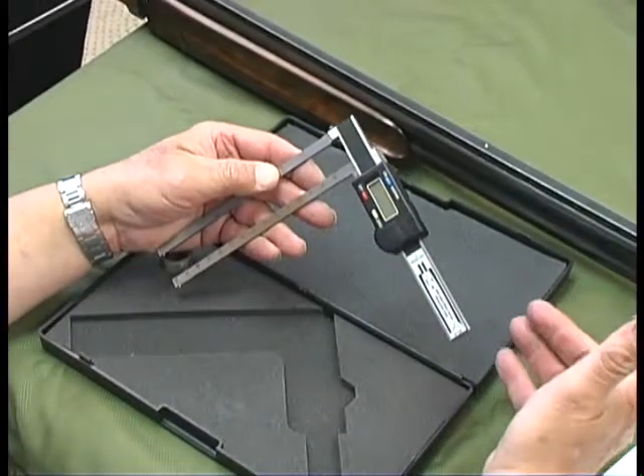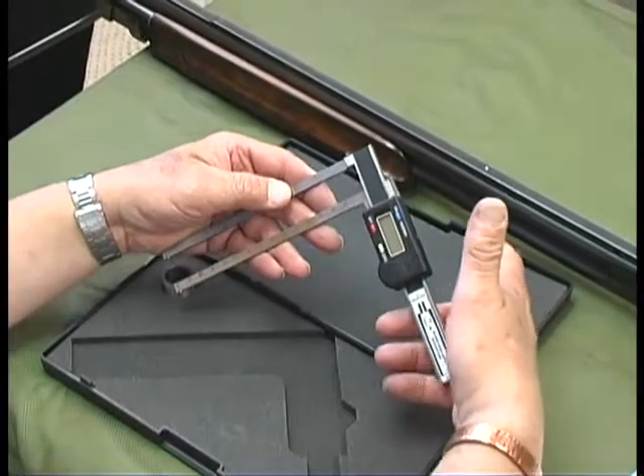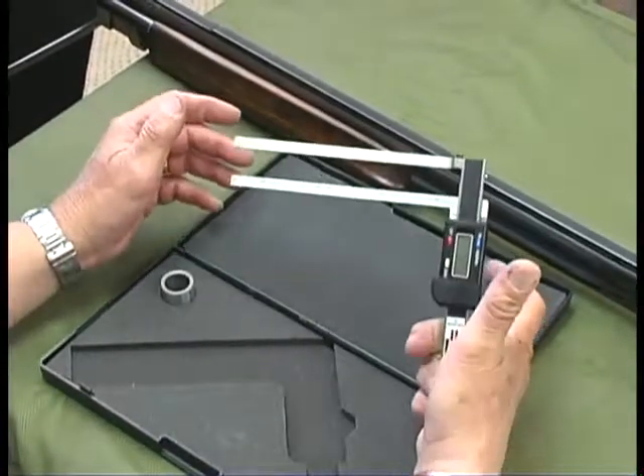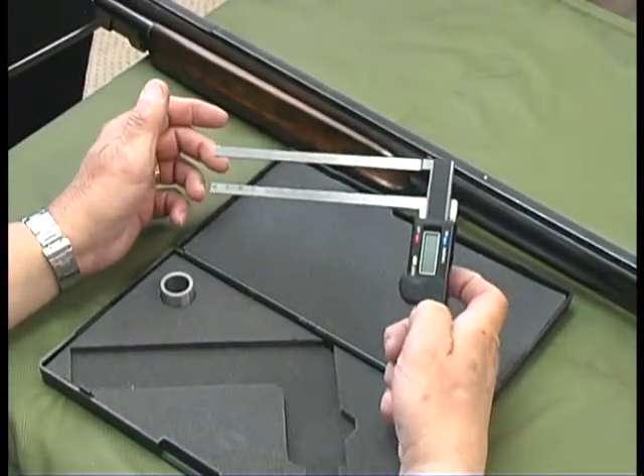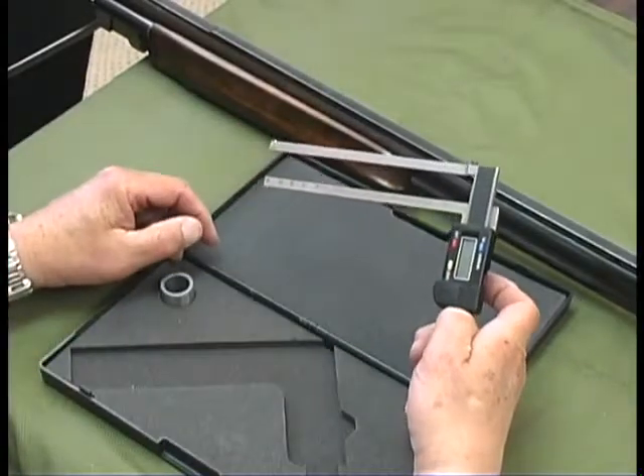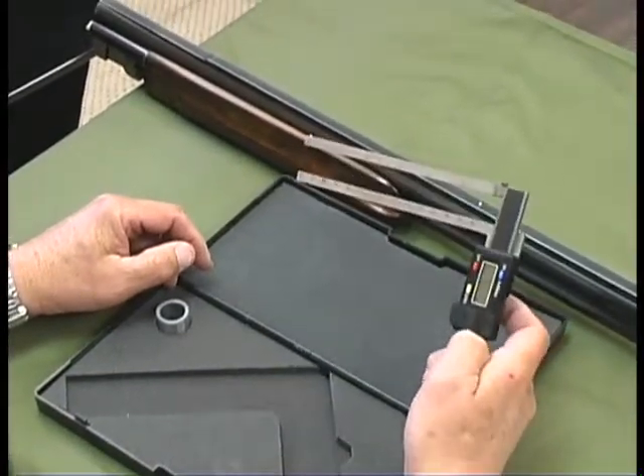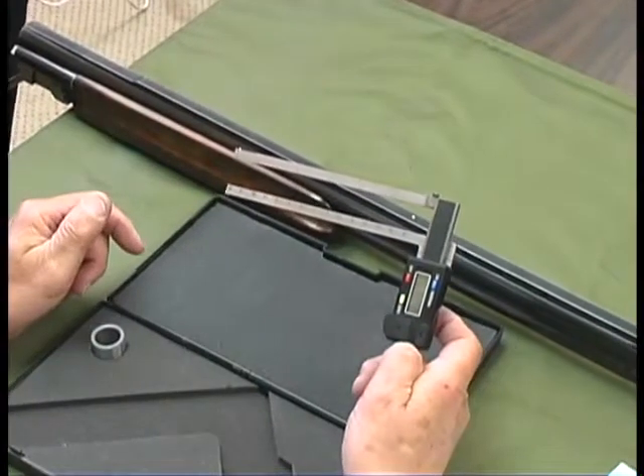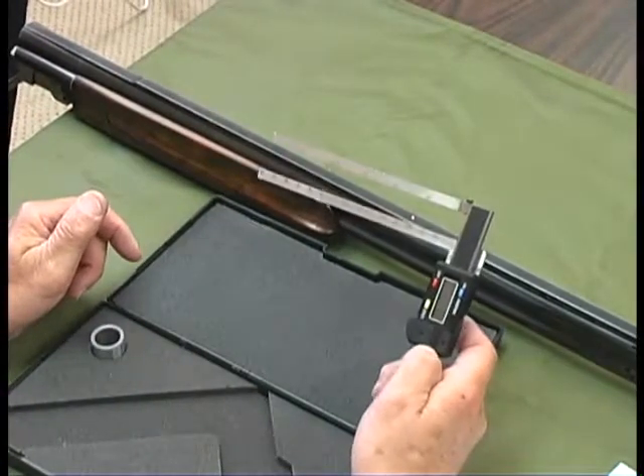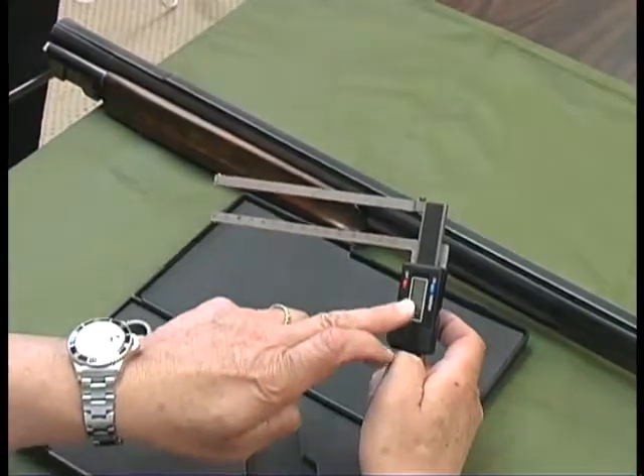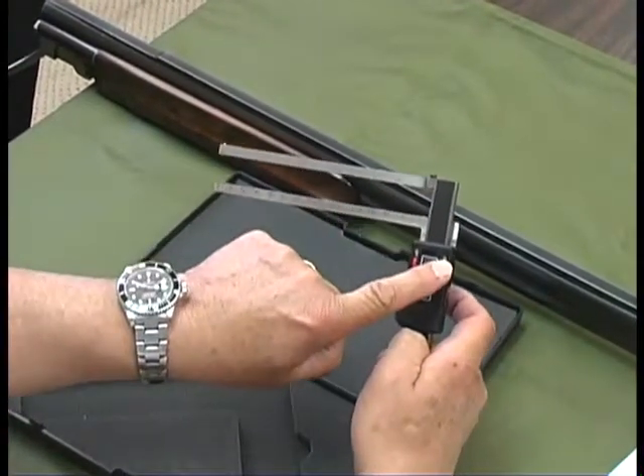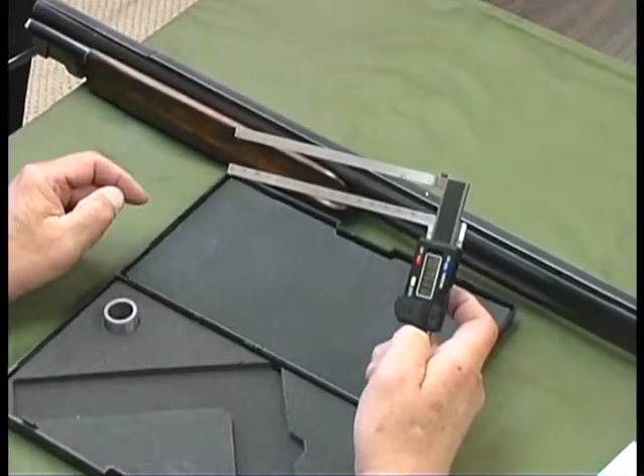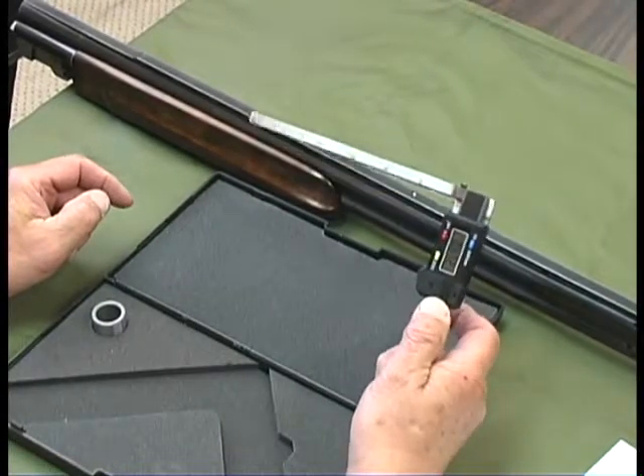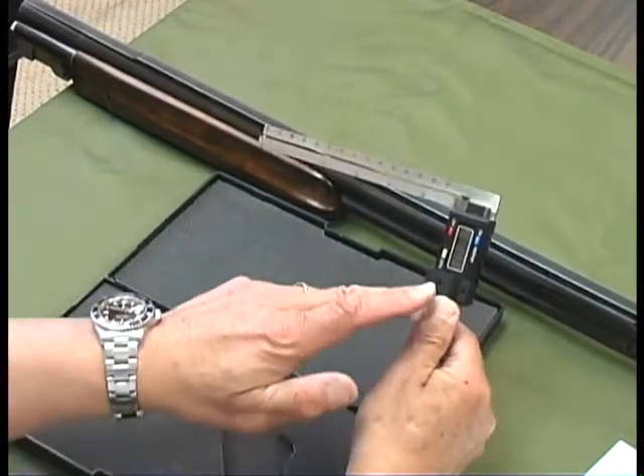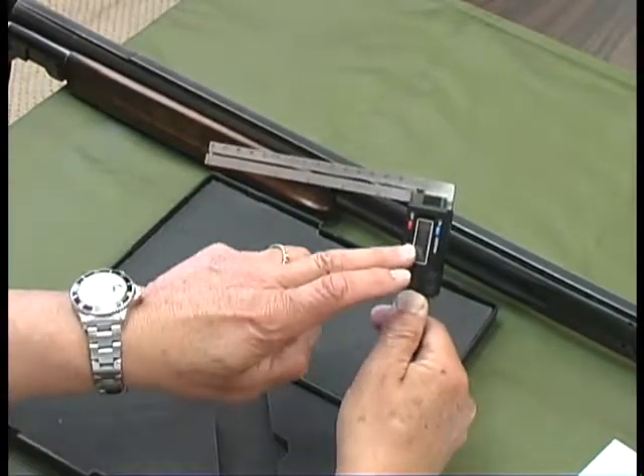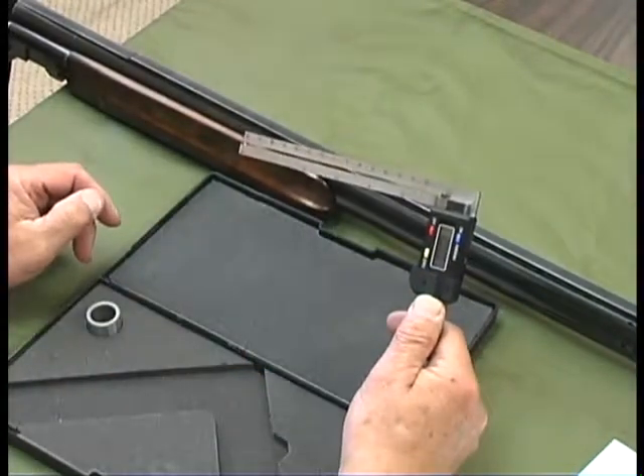When you use the multi-bore gauge, you always clasp it with three fingers, and you clasp it below any interference with the slide. As you can see, this is spring-loaded in the opposite direction that you would normally consider a spring-loaded device. So in order to arm this, we hit the blue button for on, and we push this all the way up to the top of the slide, keeping considerable pressure on your thumb, and then hit 0 to get a 0 reading.